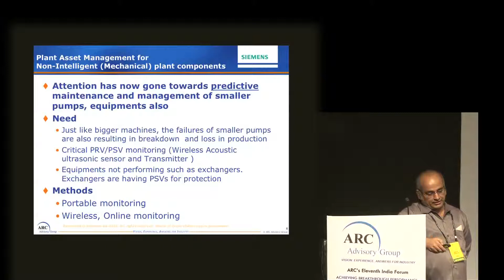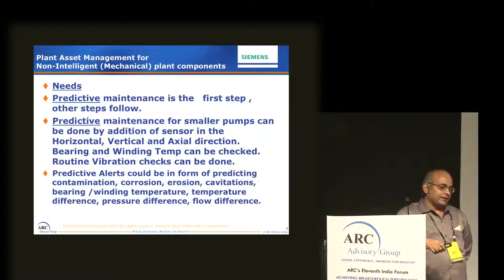Methods could include portable monitoring, wireless monitoring, or online monitoring of these systems. Predictive maintenance is the first step, with other steps following. Predictive maintenance for smaller pumps can be done by adding sensors in various directions to monitor bearing and winding temperatures. Predictive alerts could take the form of predicting contamination, corrosion, erosion, etc.